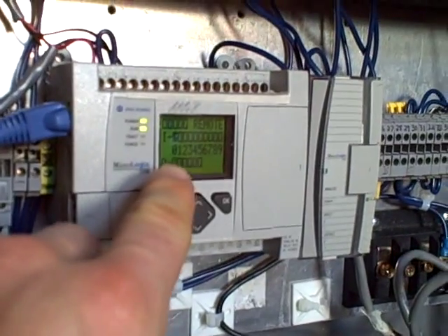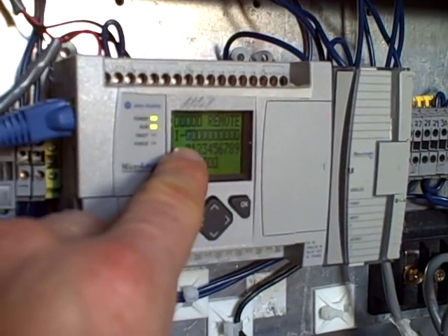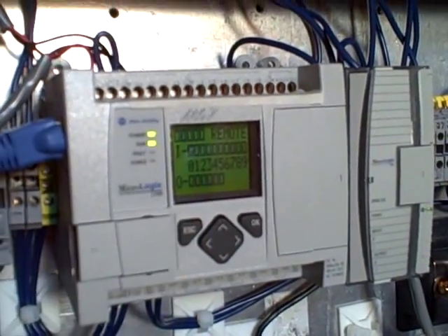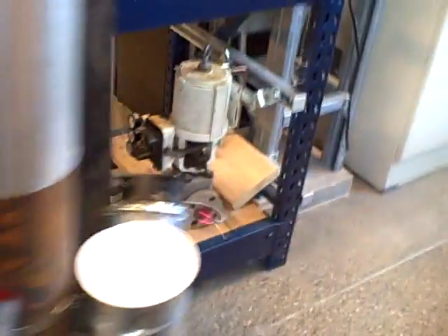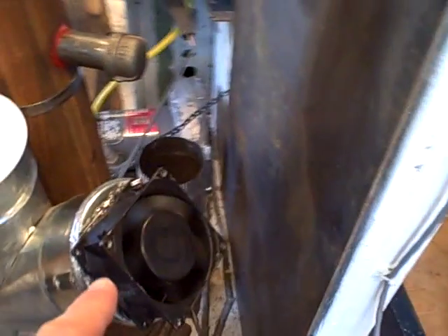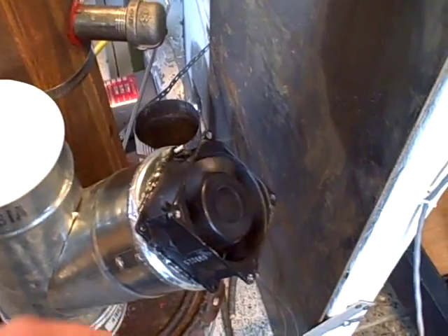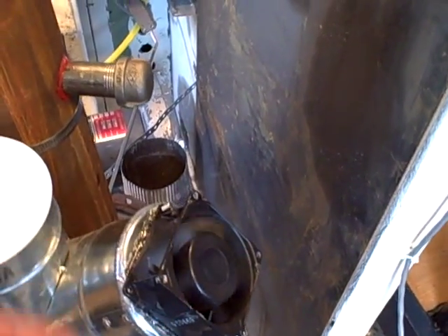And what that does at that point is send out a high-level signal, on-off 24 volts DC, to one of the inputs on our PLC. So if we took a look at the I/O status right there, you can see the first bit on the I/O of the small PLC blinking on-off, on-off. And that corresponds to the peaks of the sine wave coming out of this motor.